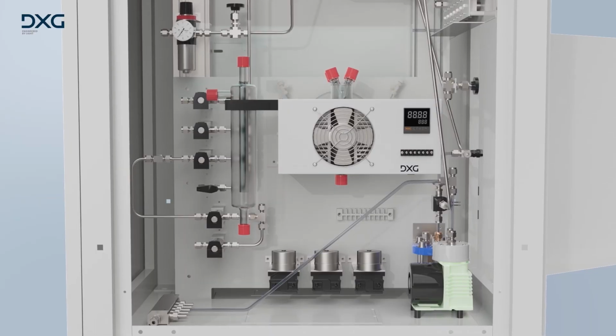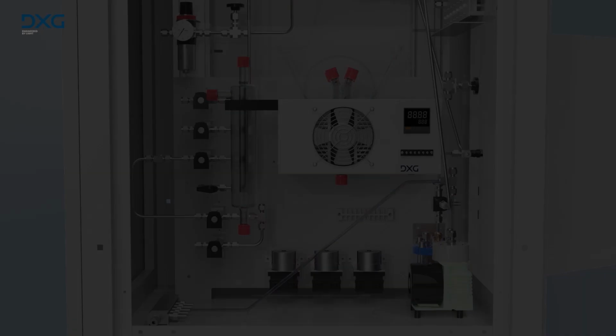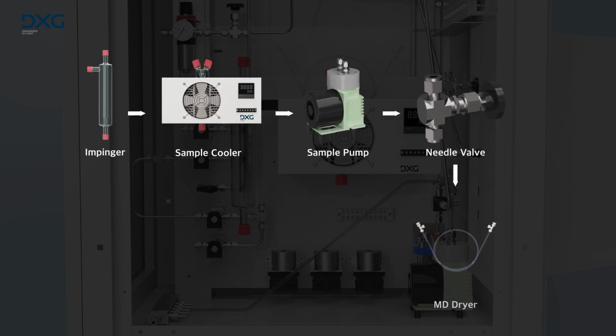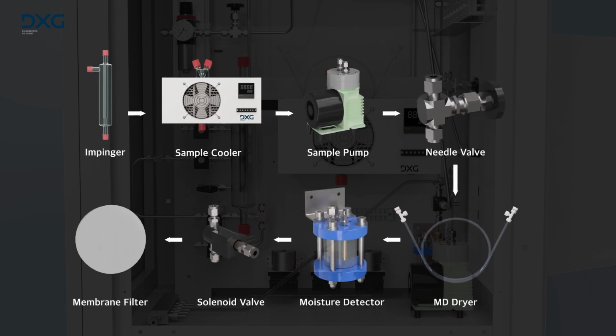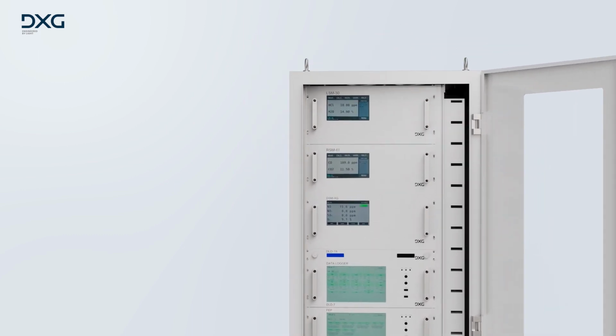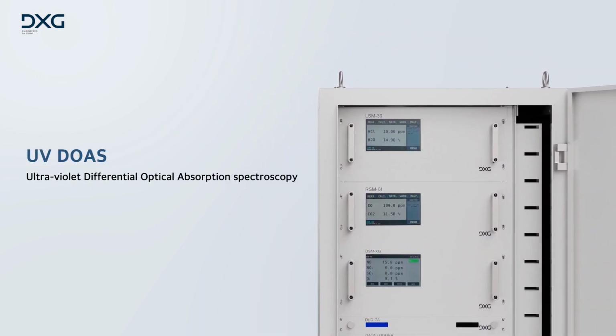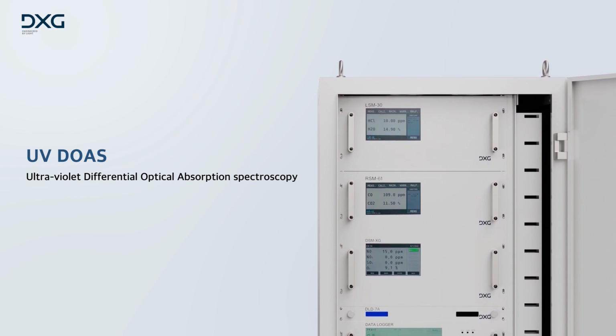As the gas enters the conditioning system, it is subjected to primary moisture removal from the impinger and electric cooler, and residual moisture removal from the MD dryer. If moisture is detected by the moisture detector, the entire sampling process will be stopped. And in case of normal operation with no moisture detected, the sampled gas will proceed to the next step where residual dust is then removed through a membrane filter. Upon the completion of the conditioning process, the sample is transferred to each analyzer for measurement.